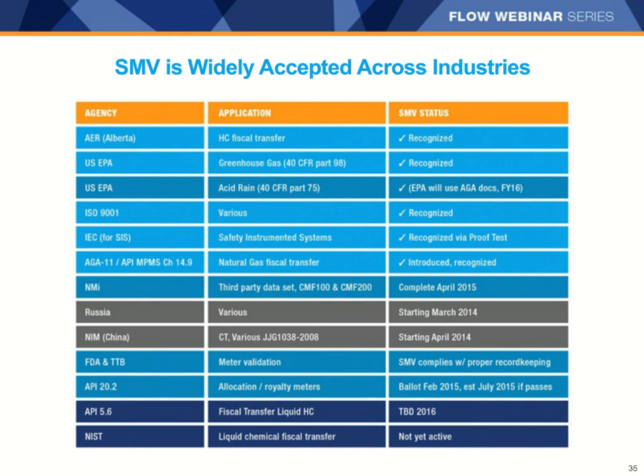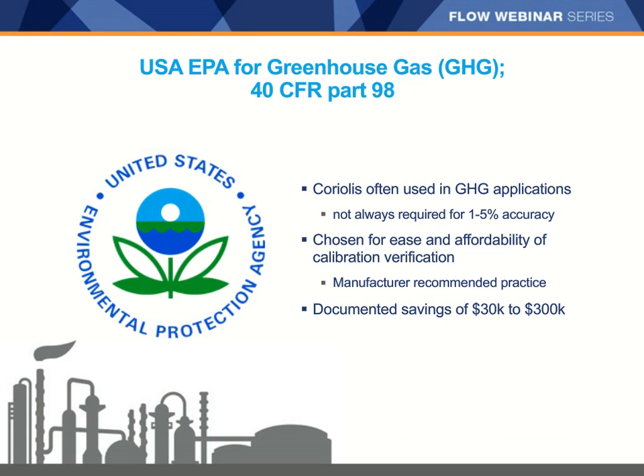I hope you enjoyed that short video on SMV. There are a number of third-party organizations that currently accept or are evaluating smart meter verification for acceptance, as you can see here in this list. One of these recognitions is by the U.S. EPA as a way to meet 40 CFR Part 98. Customers choose Coriolis here for ease of use and affordability of calibration verification. Some have saved up to $300,000 per year on reduced or eliminated calibrations.